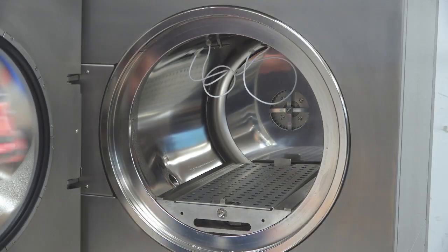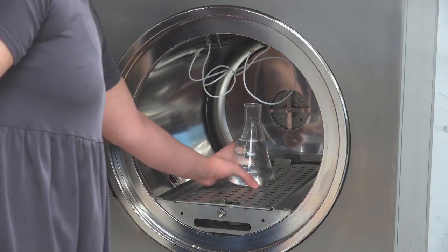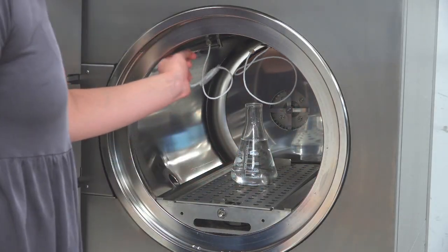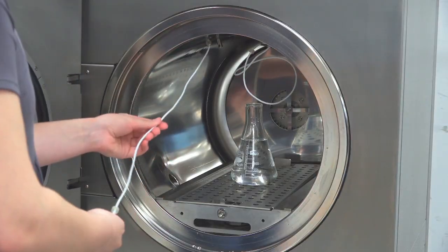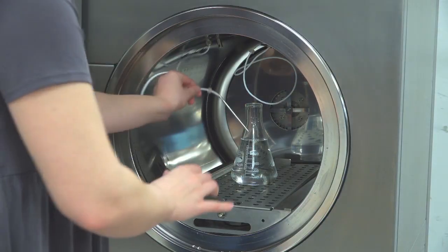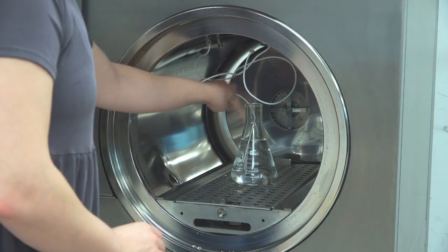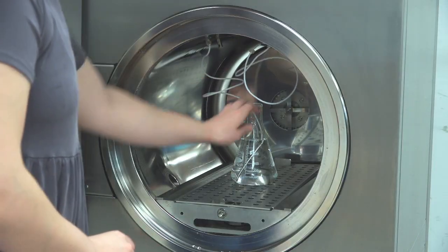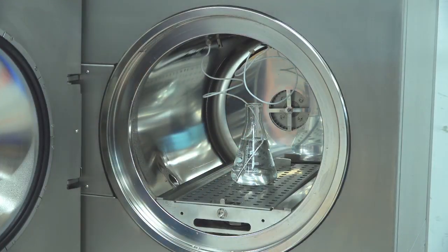The reference vessel being used should be representative of the largest volume of liquid in the load. Place the reference vessel in the center of the load, then remove the temperature probe from the ceiling of the autoclave. Pull it so it's fully extended to prevent it from recoiling, and place it inside of the reference vessel so that the end is touching the bottom of the container.